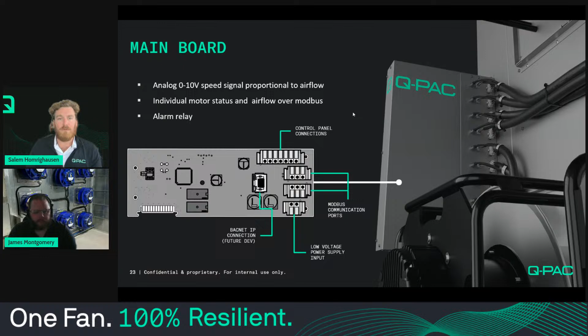Currently, it can communicate with RS-485 conductors over Modbus, and that's how you get your individual ECM plug fan status. You can get your Q-PAC fan level airflow, and you'll also get an alarm relay that tells you whether there's a failed state or not.